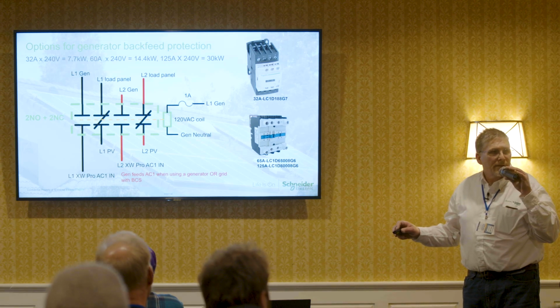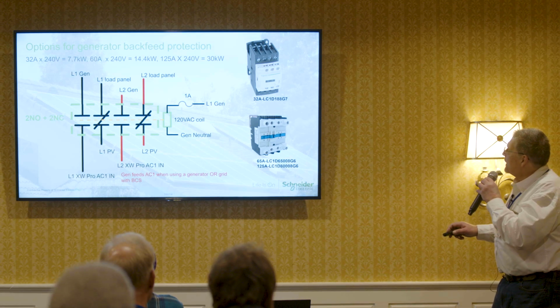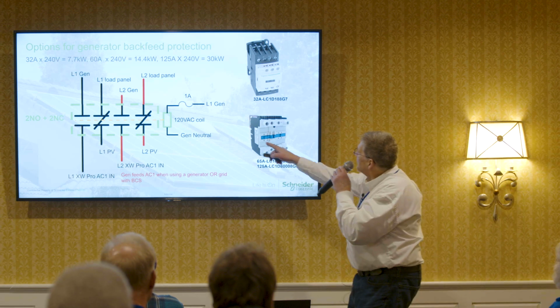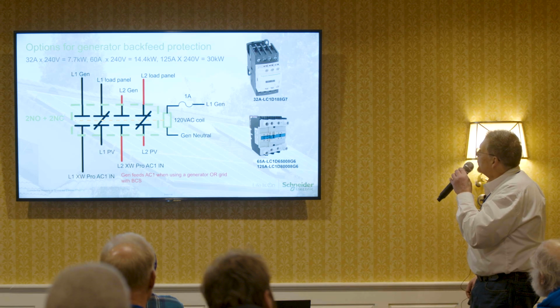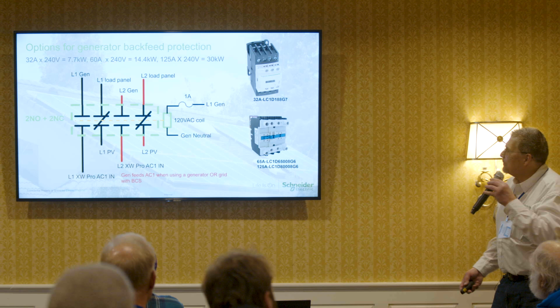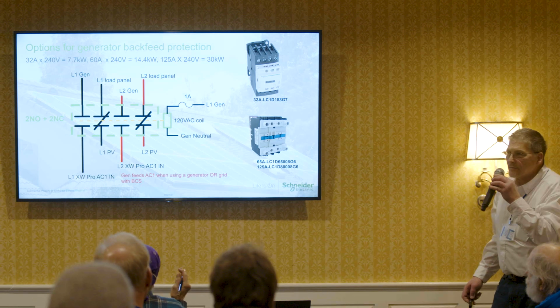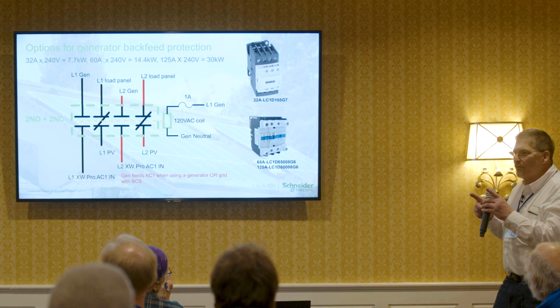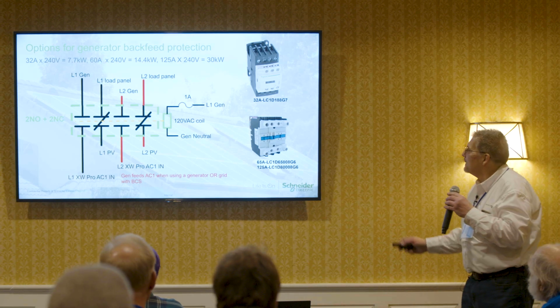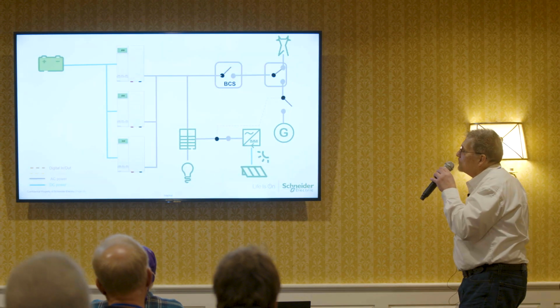You just indicated you had the DIN rail in there, and I was just wondering, that's important, so that's fine. Yeah, I can see this one looks like it can be mounted on a DIN rail, and I don't see why you couldn't do that, right? You're within an enclosure. It should be perfectly legal. What's the space of your DIN rail? It's like 4 inches. I'm pretty sure it would fit. If not, you can install a box outside to mount it in. You could even put it in the PDP if you chose to use one.